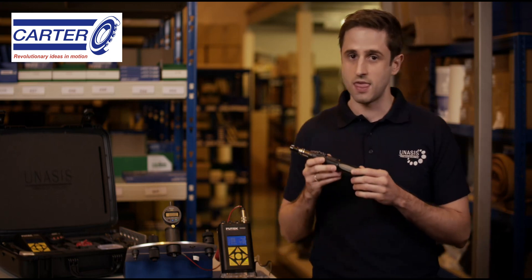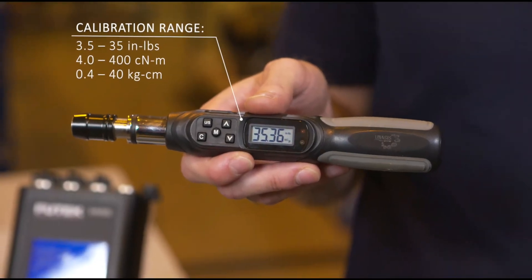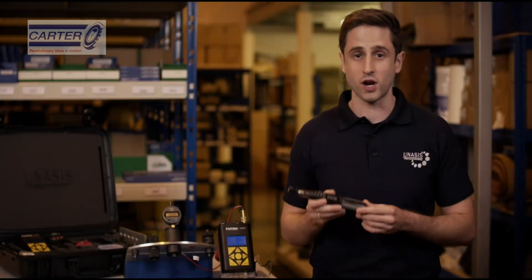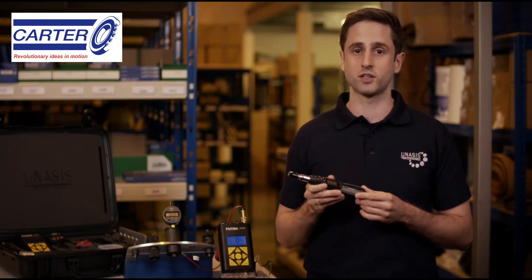The main benefits of this tool are that it's completely portable, accurate, consistent, and easy to use. Within this kit we have the UNASIS Digital Torque Wrench. This particular wrench is calibrated between 3.5 and 35 inch-pounds, and we also have options for higher and lower torque ratings. The wrench has settings for both tracking torque and peak torque. For this test we'll be using the peak torque setting, which will provide our breakaway torque value.